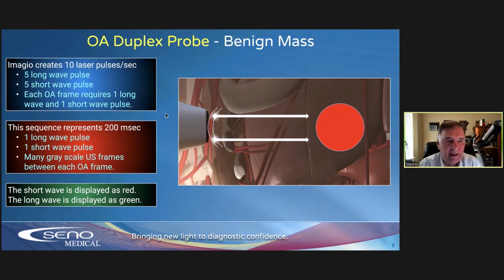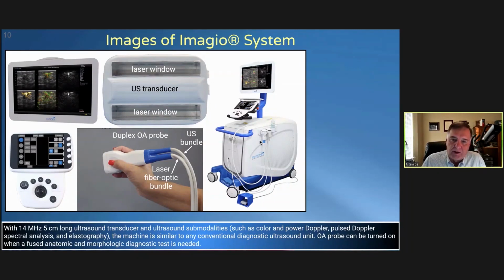Now we can fire about 10 pulses per second, not because of computer limitations, but because we have to allow enough time between pulses for the slight heat that's generated to be dissipated by diffusion and/or be carried away by flowing blood. But to generate a frame of OA, we need both a long wave and a short wave, waves that are designed to be absorbed in oxygenated and deoxygenated blood. So we can essentially generate 5 frames a second of OA, and each frame takes about 200 milliseconds to create. This is the Imagio machine on the right.